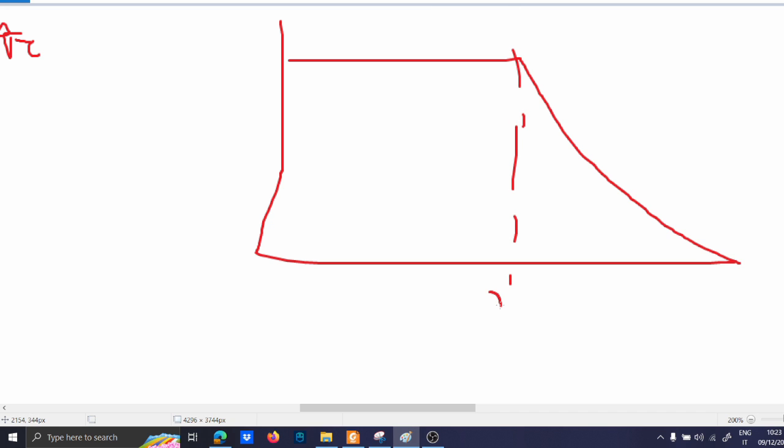This is the speed, omega m, or let us say 60 Hz. If you use the flux weakening technique, you can increase the speed. This is the speed, but the torque will go down.